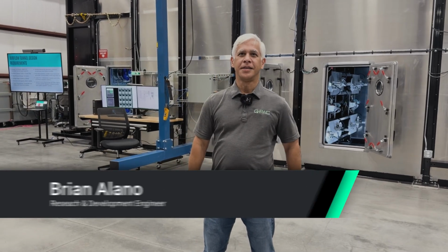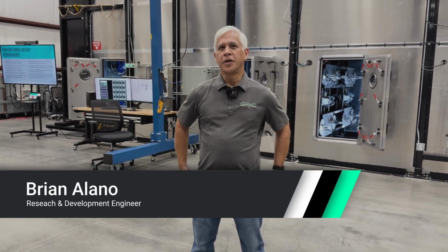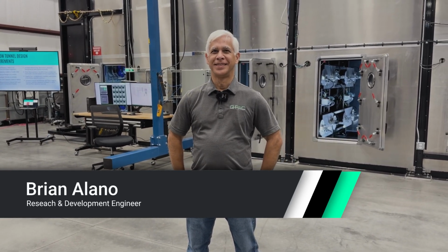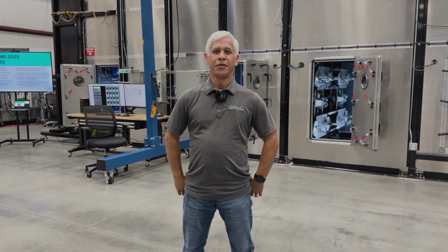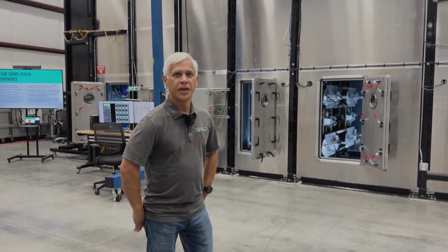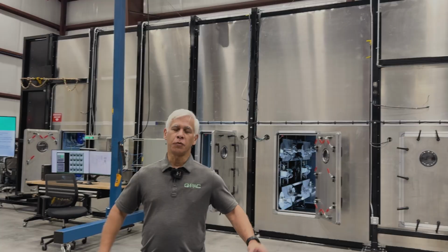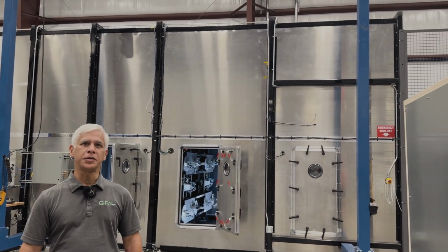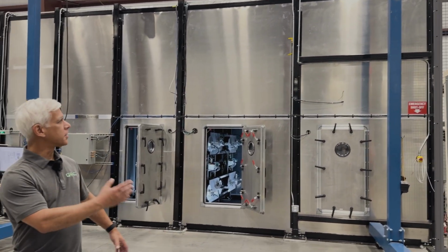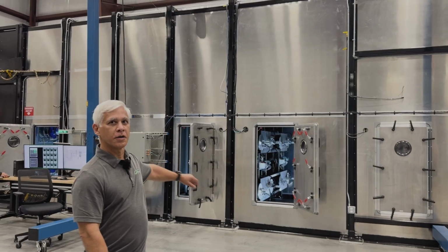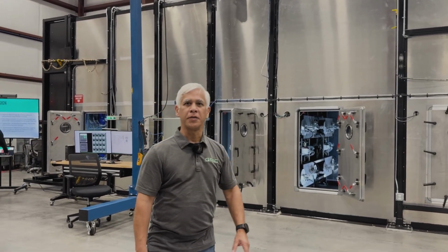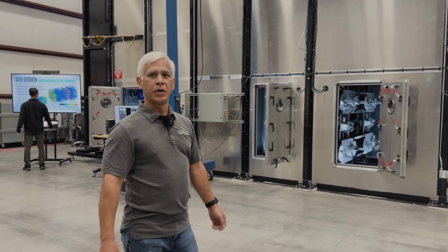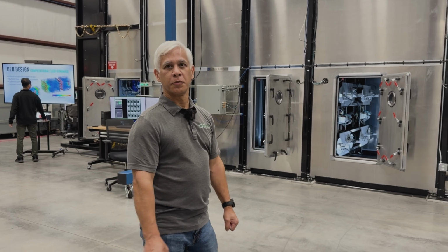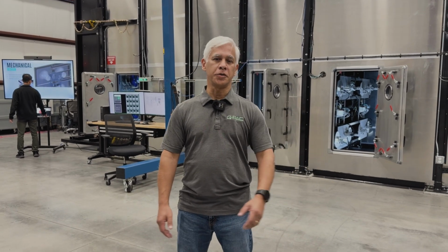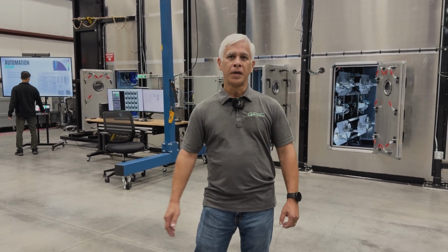So we're standing in front of Q-PAC's airflow tunnel? We are standing in front of Q-PAC's airflow tunnel. All right, let's just start with the basics. What do we got? What do you have? We have a 12 by 12 foot wide by 12 foot high airflow tunnel. On our right side, we have our test fans. On our other side, we have some supply fans to push air through there. We can get 70,000 CFM through this tunnel, all the way down to 2,000 CFM we can measure.